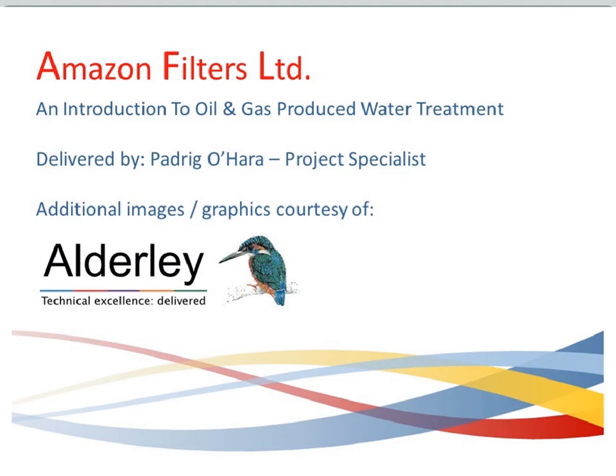Now, I've got a question here, similar in a way, on environmental effects of disposal of produced water in offshore situations, which I believe you can re-inject produced water, but it can also be dumped overboard. Yes, it can, and typically is dumped overboard once it's been treated down to a very, very fine level, perhaps 10 to 30 ppm of oil. Now, the environmental standards are set by local regulators, and they will be monitoring, and the fines are very significant for any oil companies that breach those environmental standards, combined with the reputational damage that will be done to those oil operators. So there is a huge incentive for the oil operators to ensure that they do comply, and they are very, very strict on their monitoring, and they will close down operations if they are going to be in breach.